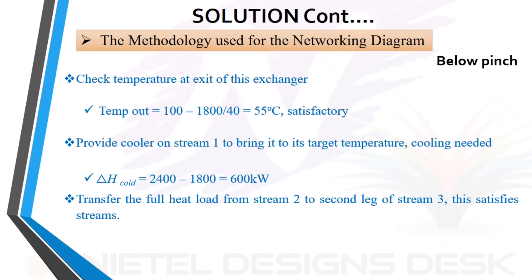Check the temperature at the exit of this exchanger. T_out equals 100 minus 1800 over 40 equals 55 degrees Celsius — satisfactory. Provide a cooler on stream 1 to bring it to its target temperature. Cooling needed: H_cold equals 2400 minus 1800 equals 600 kilowatts.